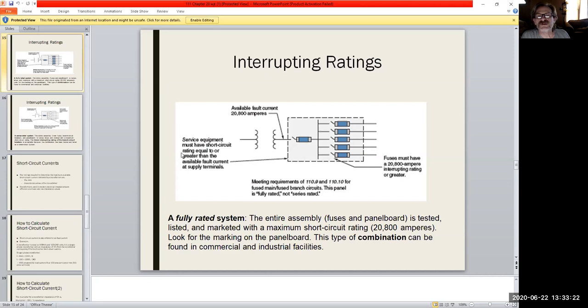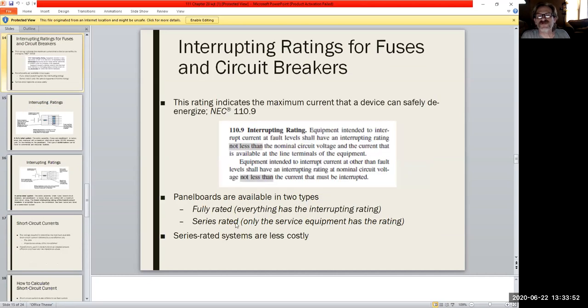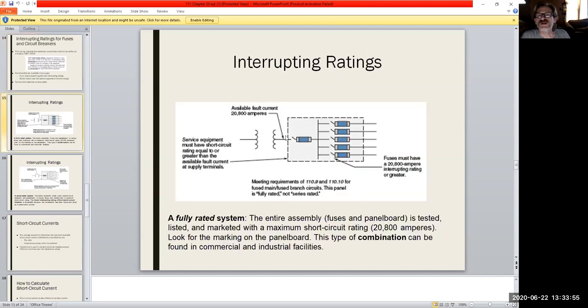Service equipment must have a short circuit rating equal to or greater than the available fault current. So if we look at what our fault current is in this case, you can see 20,800 amps, which is quite large. But again, the service equipment should be rated for that. So you would be able to see on there somehow that it's labeled to handle an interrupt of 20,800 amps or greater. Now that's in a fully rated system. With the series rated ones, this listing would not be available. But in this case, if our panel meets our requirements here, then it'll be a fully rated panel able to handle a fault current of this amount with no damage, or minimal damage, as opposed to the series rated system.